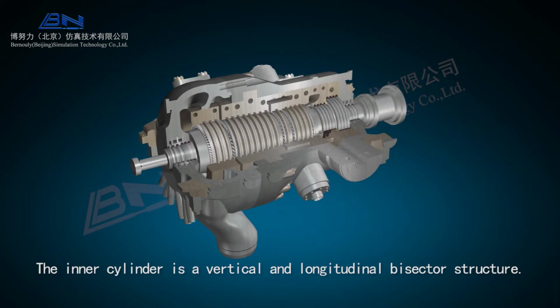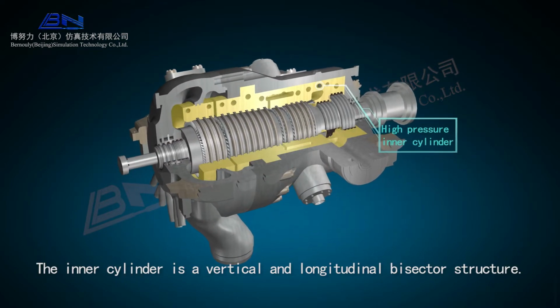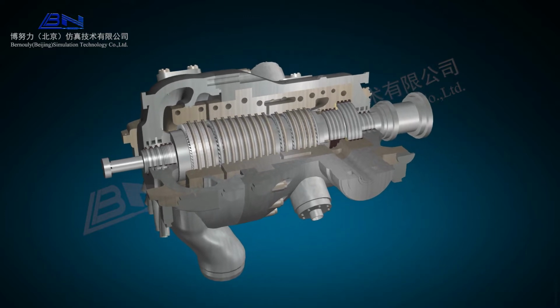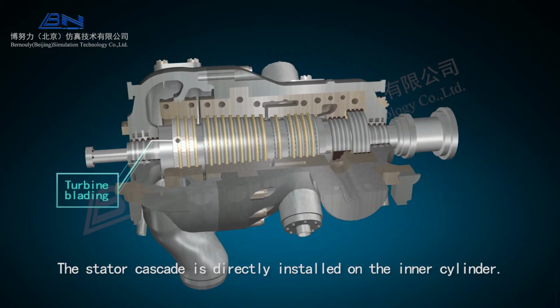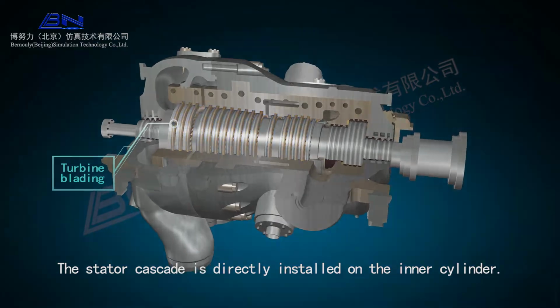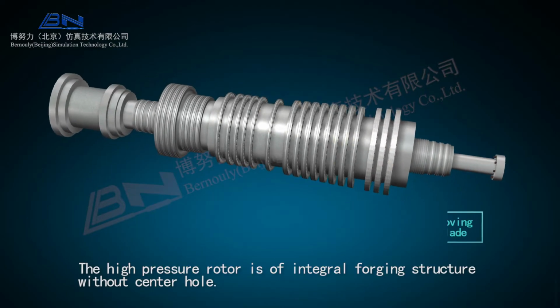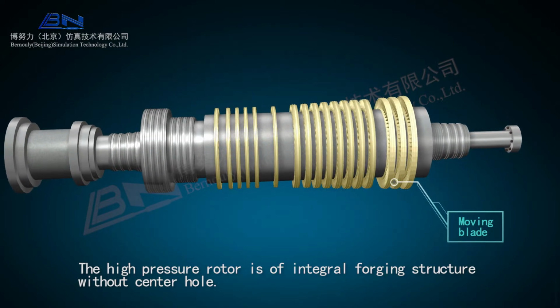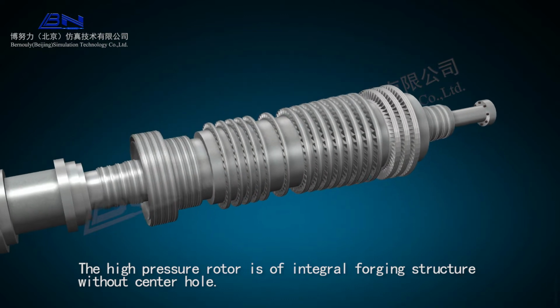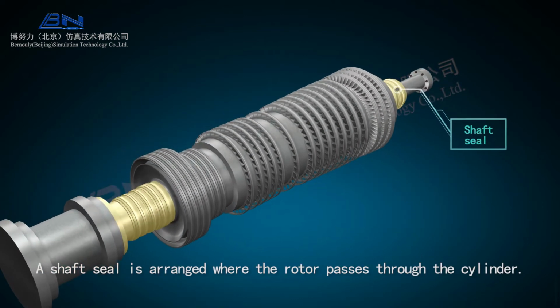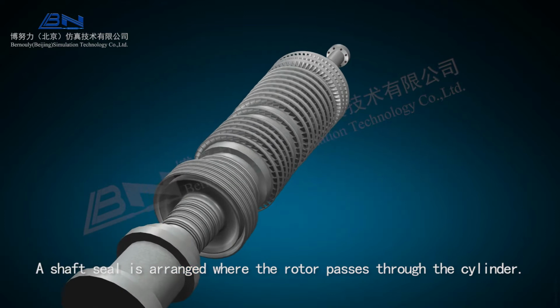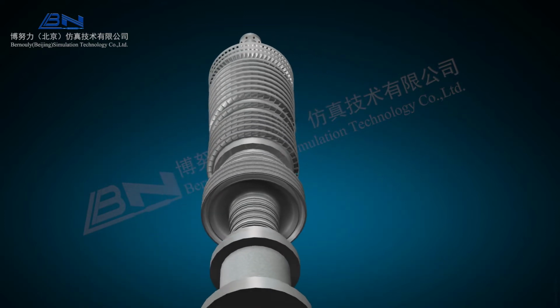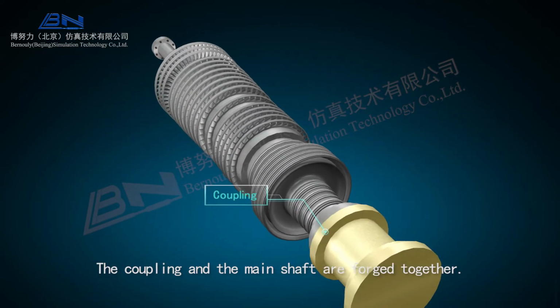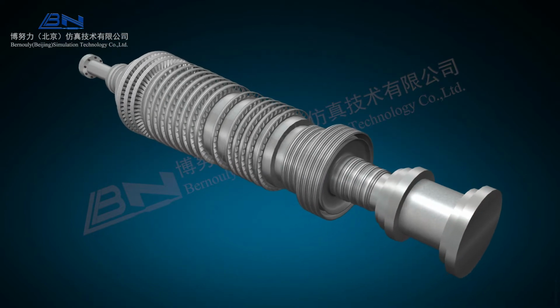The inner cylinder is a vertical and longitudinal bisector structure. The stator cascade is directly installed on the inner cylinder. The high-pressure rotor is of integral forging structure without center hole. A shaft seal is arranged where the rotor passes through the cylinder. The coupling and the main shaft are forged together.